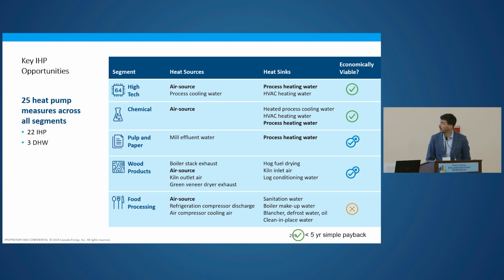Some of the main opportunities: we came up with 25 heat pump opportunities. Of these, a couple were domestic hot water, but the vast majority were industrial heat pump. Looking at this table, you could see that there were a variety of sources and sinks. I wanted to point out some of the commonalities. One of these is using air as a source, and the other is a sink being process heating water, which was fairly common in some of the segments.